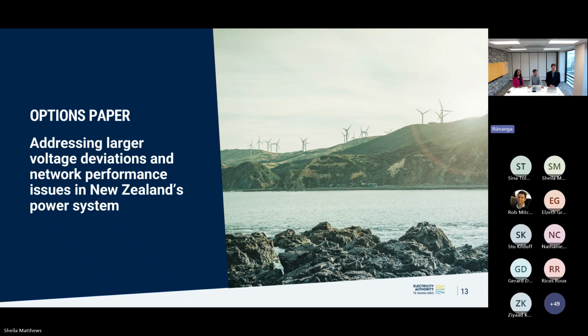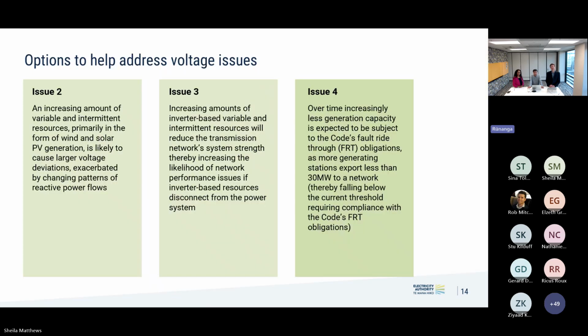The other paper is around voltage, and there are three voltage-related issues here. The first of these is that, again, increasing the amount of variable and intermittent resources is likely to lead to more voltage deviations, larger voltage deviations, in the power system. You'll see a reduction in the power system strength, which reduces the quality of the voltage waveform, and as a result of that, we get these deviations. And over time, what we're seeing is changing patterns in reactive power flows, and that's exacerbating this issue, and will continue to do so as you see more reactive power coming into the transmission system from distribution networks.